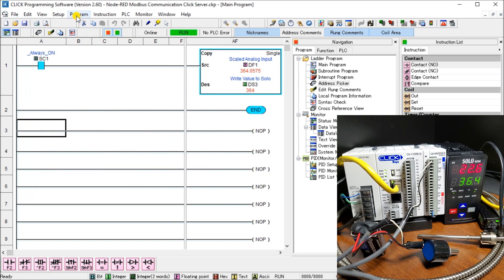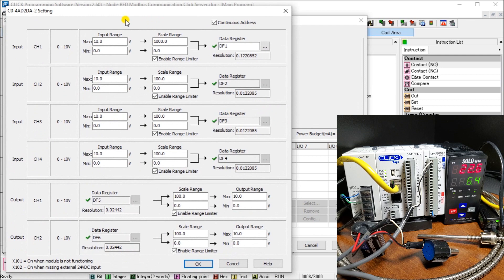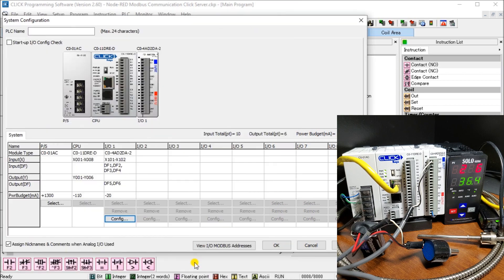Under System Configuration, you can see the power supply, CPU, and analog card. In the analog card configuration, the input is scaled from 0–10 volts (0–9 volts in our case) mapped to 0–1000, placed in DF1. The value 1000 represents 100.0, since the decimal point is already included — so 1000 equals 100.0 degrees.